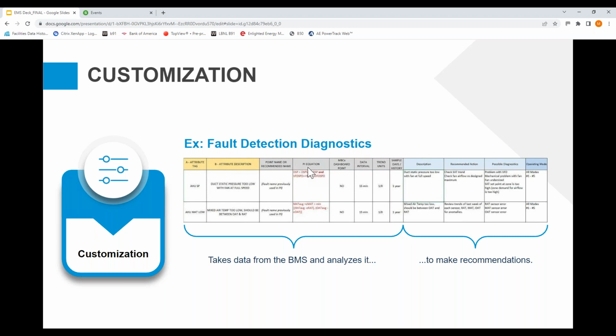What is it? Well, it's actually quite similar to analytic software, which we talked about on day one. It is taking pieces of information, putting it in an equation, and then kind of spitting out a result. When we talked about the analytics software, we used an economizer as an example, where it's looking at a lot of different data points from temperatures to valve positions or damper positions, and saying whether or not your system is performing or in economizer mode when it should be, hopefully saving energy.